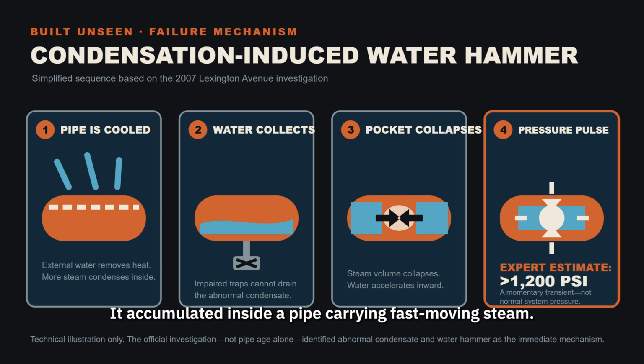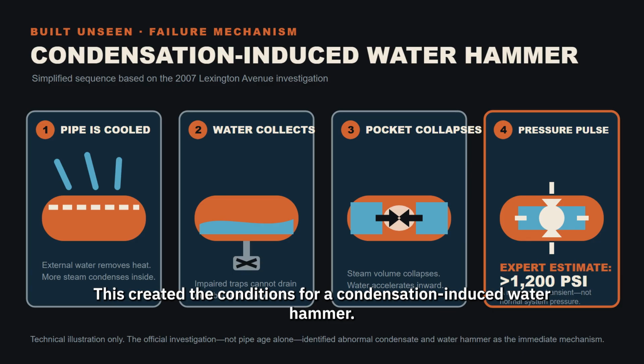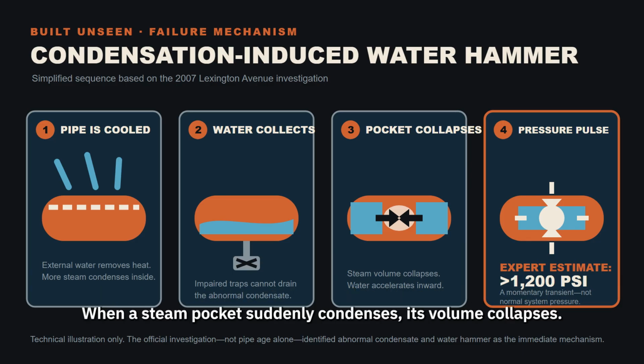Liquid accumulated inside a pipe carrying fast-moving steam. This created the conditions for a condensation-induced water hammer. Imagine pockets of steam trapped between moving slugs of water. When a steam pocket suddenly condenses, its volume collapses. Water rushes into the space from both directions. The collision produces a short, extreme pressure pulse.